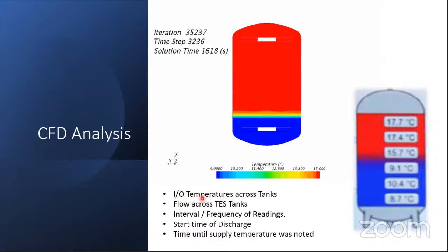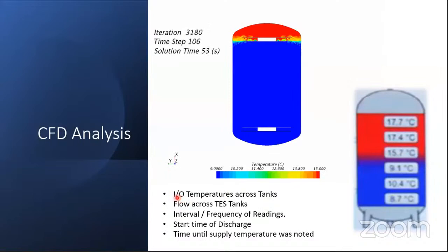So, inlet outlet temperatures across the thermal storage tank. I would also want to highlight here the important parameters with respect to which these systems are commissioned. Once the CFD analysis is done, that of course becomes a reference point for how the thermal storage system will perform. But inlet outlet temperature across the thermal storage tank is recorded. Flow across the thermal storage tank is also recorded. Now, with inlet outlet temperatures and flow, we can figure out the tonnage. What is the tonnage that is being delivered?